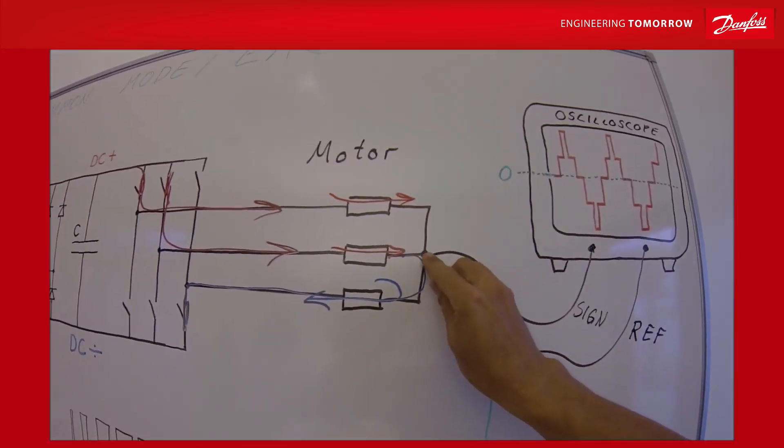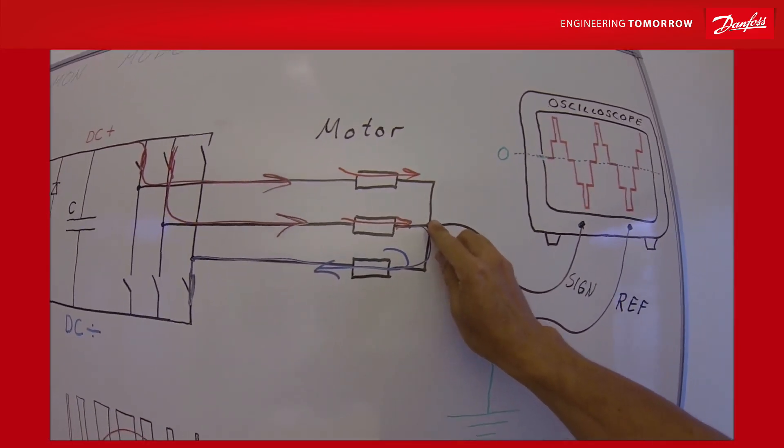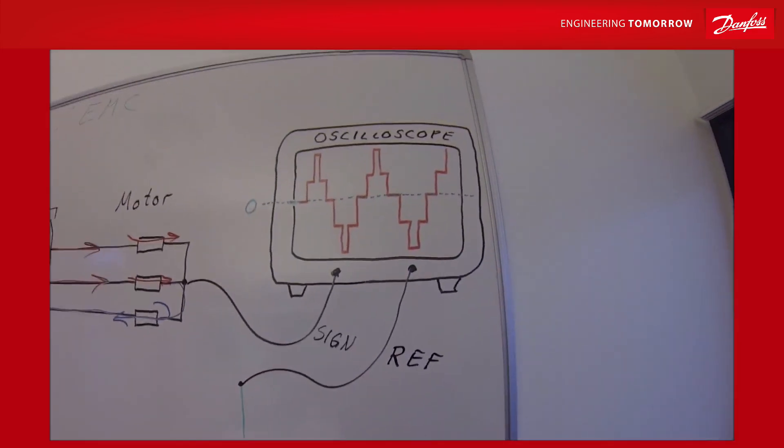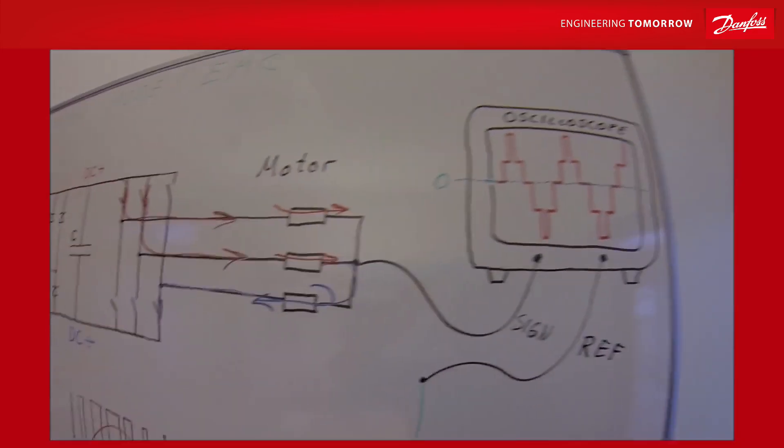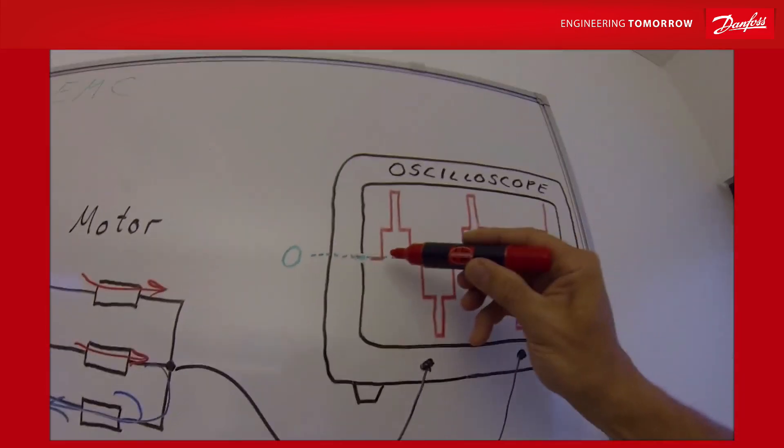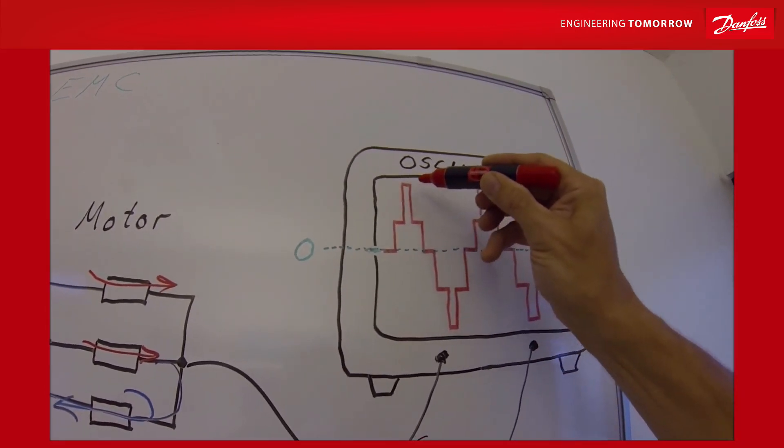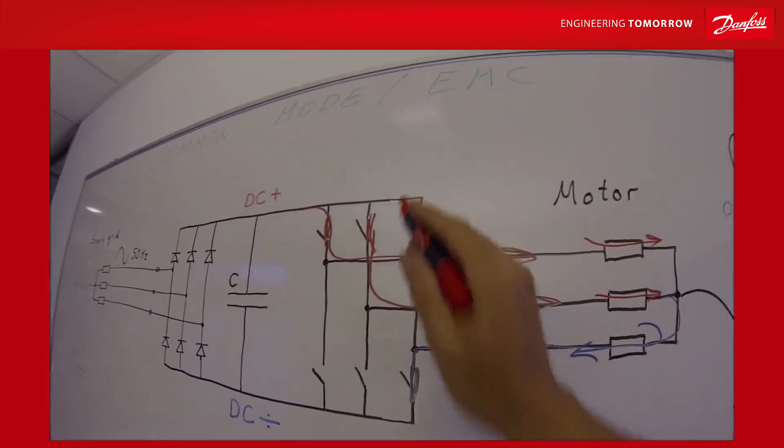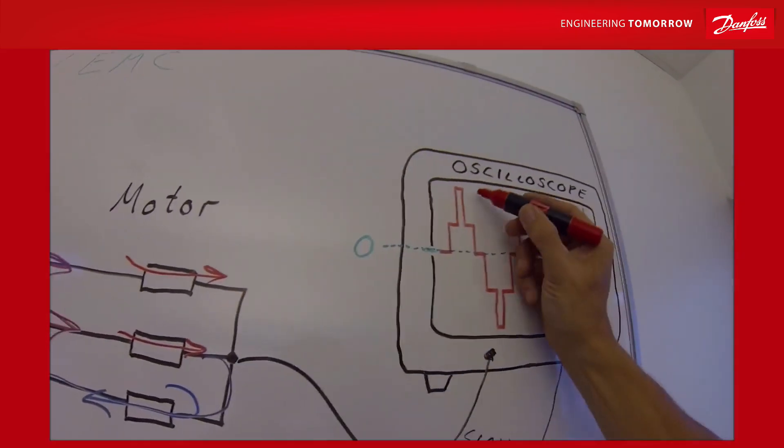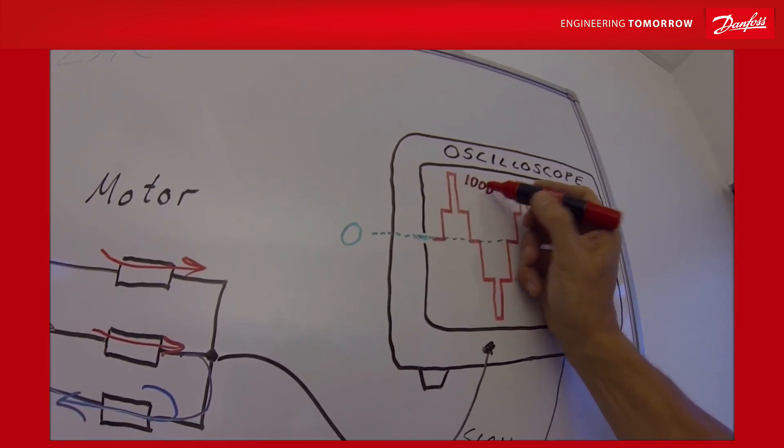What happened with this neutral point in the motor then? Well, if you look at it in our oscilloscope, we will see that we actually have lifted the star point up. And this can be quite high. It can be the full DC voltage, so we are talking about here 1000 volts.